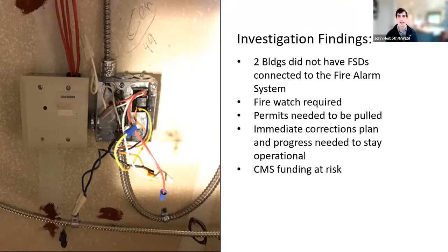And this is a life safety issue, so I told them we need to start talking, because talking with your fire marshal is a good thing. We need to have a plan in action. We need to notify the parties, and this could become a really bad thing. The reason why the fire marshal needs to get involved is because of how long it's going to take to correct. We also had a fire marshal on site that had told them they needed their dampers tested because of increasing enforcement. So it was already on their hit list for the fire marshal, and so we wanted to make sure that that didn't ratchet up.